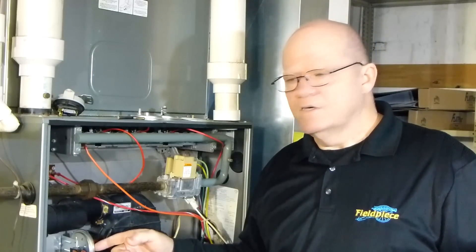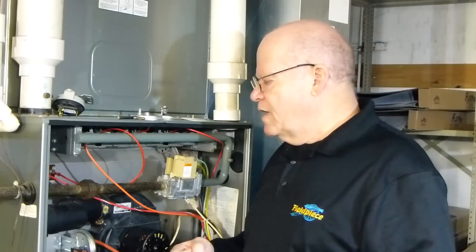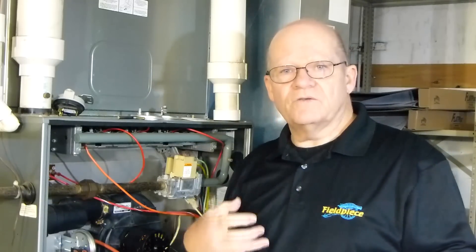The pinch method, even though you can come close, doesn't tell you anything about what's going on inside the switch. And like I said before, just because it closed doesn't mean it's good.